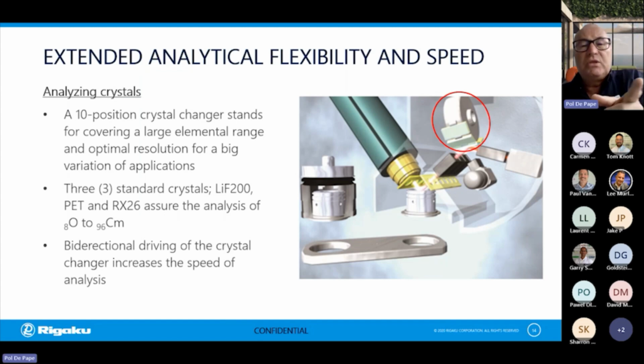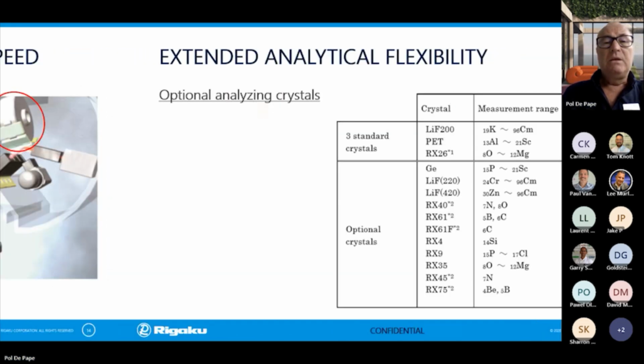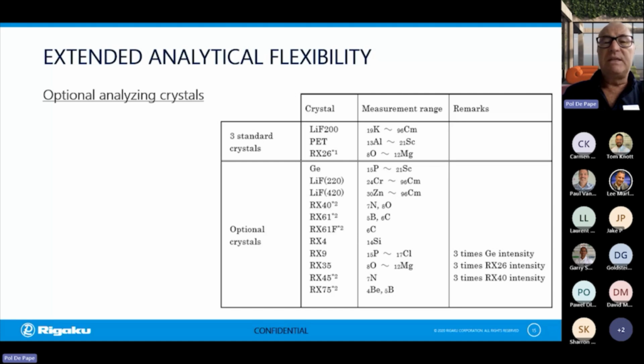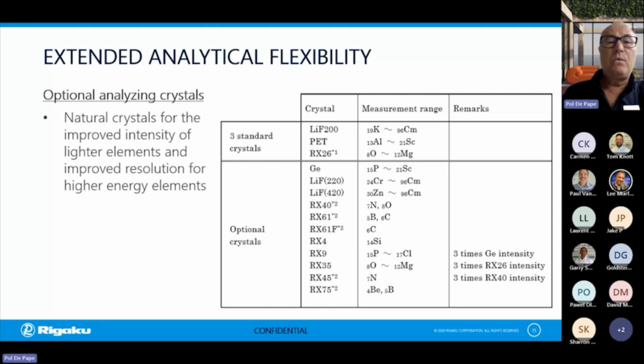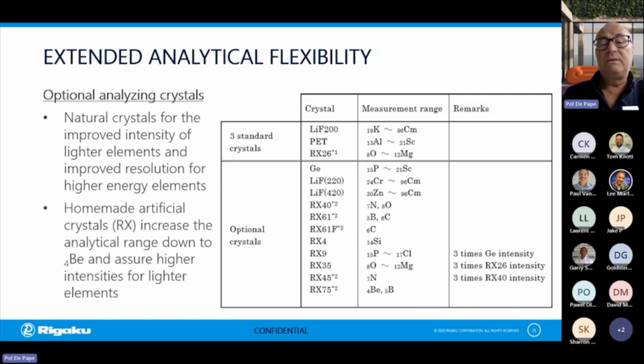This means you do not lose time having to let the mill turn at any time in one direction. So we can let it turn in any direction, left or right. So we have 3 basic crystals as mentioned, and then we are using natural crystals like the LiF200, like the PET, like the germanium, or we use homemade, Rigaku-made artificial crystals, which are all indicated with RX. And we can see using those artificial crystals, we can go down to beryllium for our elemental range.